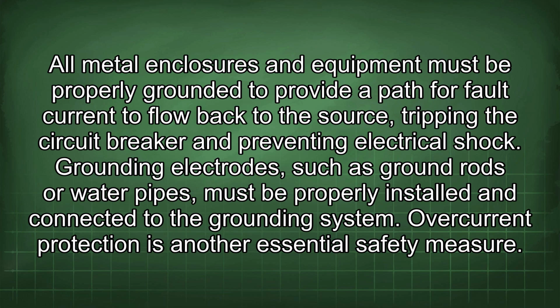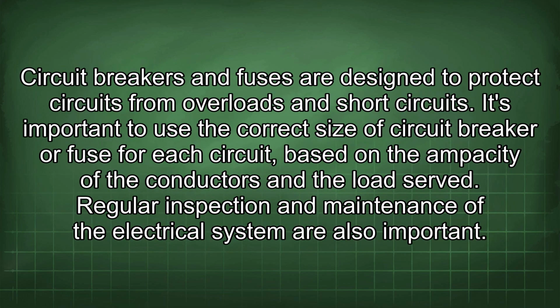Overcurrent protection is another essential safety measure. Circuit breakers and fuses are designed to protect circuits from overloads and short circuits. It's important to use the correct size of circuit breaker or fuse for each circuit, based on the ampacity of the conductors and the load served.